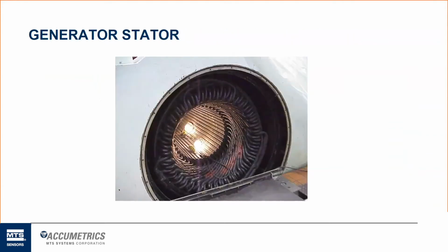Here's an example of what a generator stator may look like. Again, we're not really focusing on this because this is all stationary side of things. So that cylindrical rotor will slide down into that stator where those work lights are, to be able to create that electromagnetic field as the rotor spins around at 3,600 RPM.